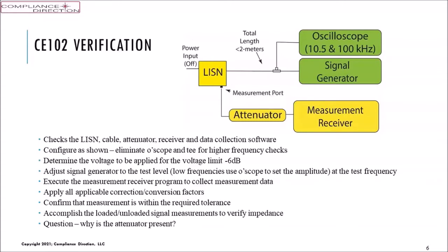Now, this unloaded-loaded test of the signal measurements is to verify the impedance. If I set these up and get my test levels with the oscilloscope being the measurement point, and I disconnect the 50 ohm termination, in other words, the LISN that comes away from that cable, the signal generator is no longer loaded by 50 ohms. It's an open circuit out there. So the oscilloscope voltage will rise dramatically because the loading effects are gone. So we measure what the oscilloscope voltage is and determine how much it changed from the loaded measurement where the LISN was connected. For 10.5 kilohertz, we should elevate about 14 dB. So the ratio is about 14 dB. If that is in fact valid, then it indicates that the impedance of our LISN is correct. It's within our tolerance range. So that's the part B step that got added for the 461G.